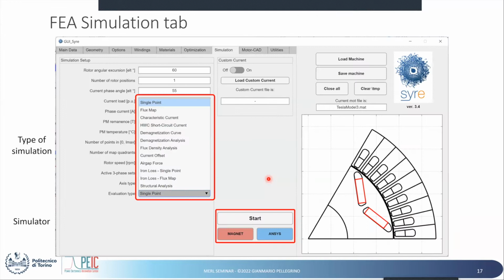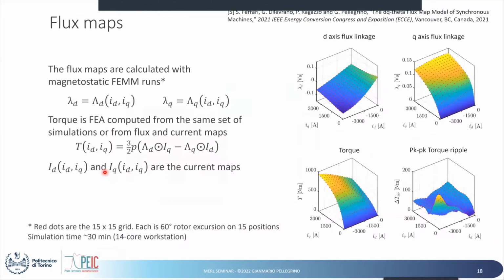And then we have a comprehensive simulation tab. We can do many things. We can do magnetic simulation and also structural analysis. And magnetic simulation leads, for example, to the D and Q axis flux linkage map. This is the footprint of the motor.